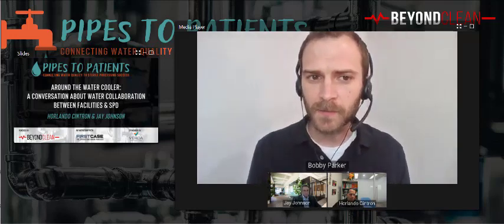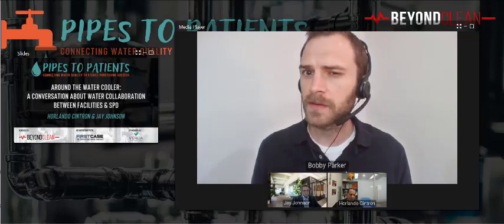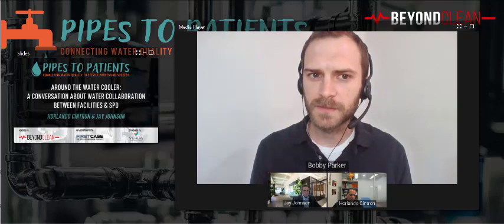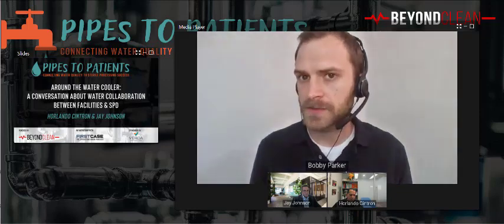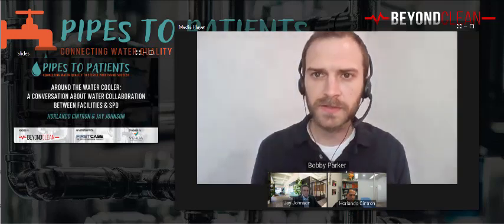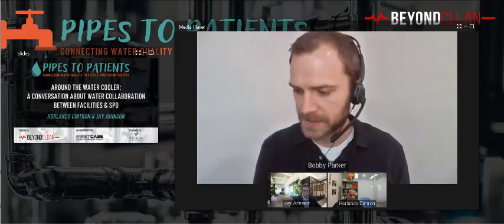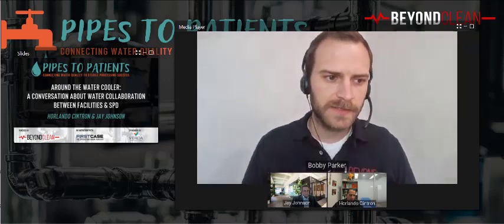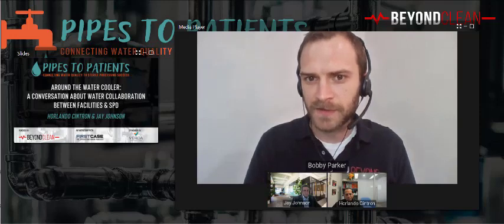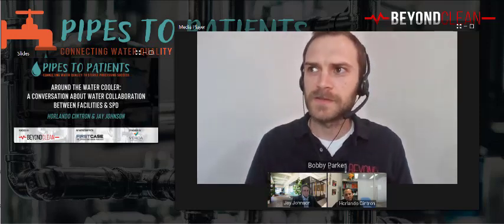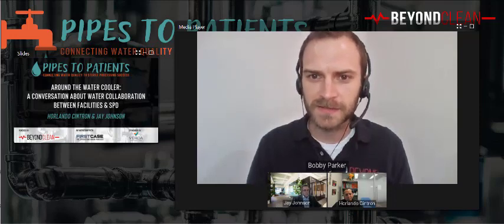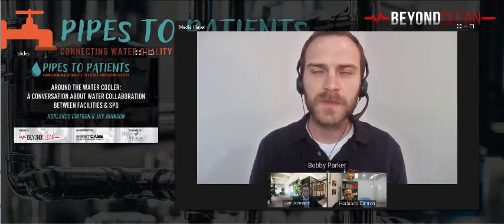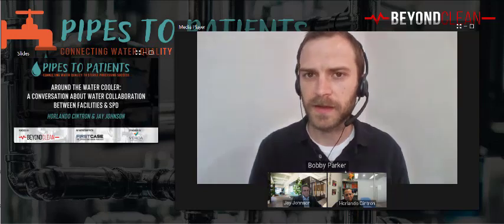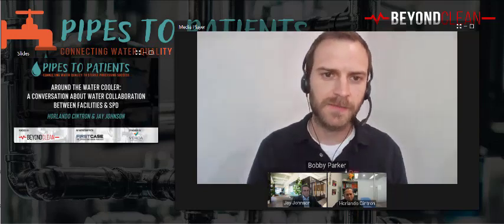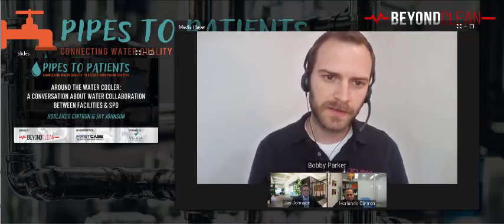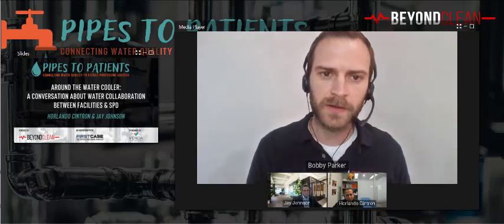Or it could be something a lot more subtle, and equipment failures that are hard to detect are perhaps the times when it's most difficult to be collaborative. I'm thinking of things like a water softener not working the way it should, and we notice the detergents aren't as effective in sterile processing as they used to be. Or sterile processing randomly starts detecting sediment in the water in the sinks, little flakes coming out, and it turns out facilities was blowing down their boiler and doing maintenance on it, and some sediment ended up downline in the sinks. Those smaller, daily maintenance equipment issues can sometimes make it difficult for the clinical team and the engineering team to see eye to eye, both on the clinical importance and on having the equipment working properly.